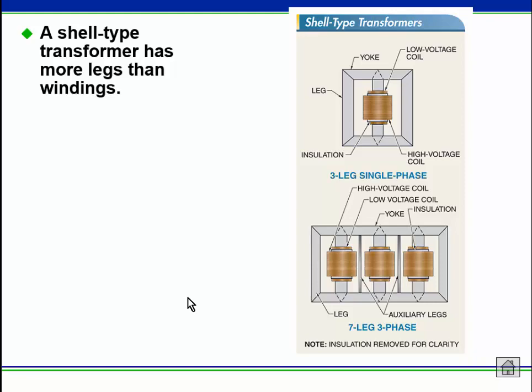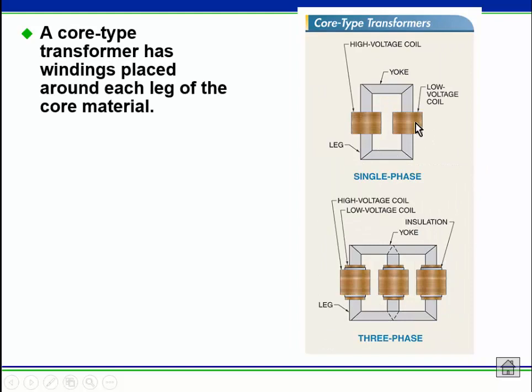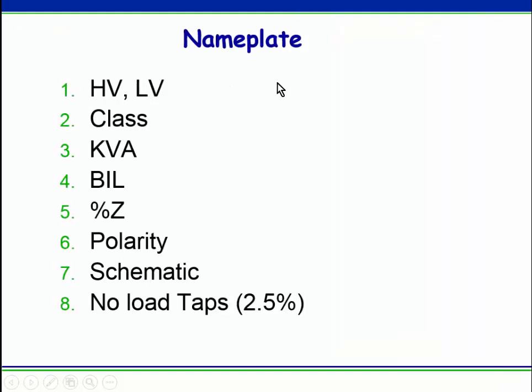All this means is shell type, there's some extra steel in the transformer, this extra steel on the outside. Whereas core type, you don't have that extra steel. You use the tank to kind of complete the circuit. So shell type has some advantages, however it's more expensive.